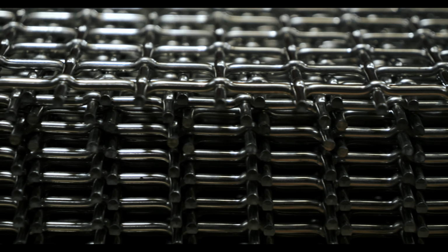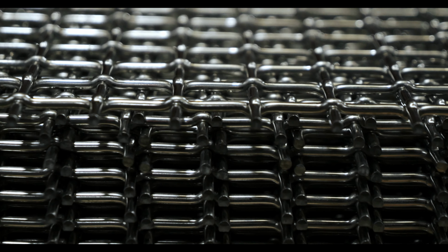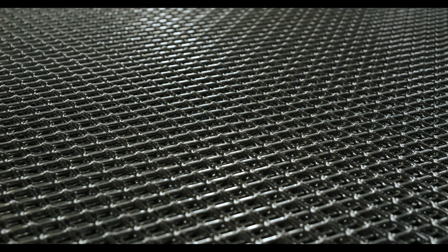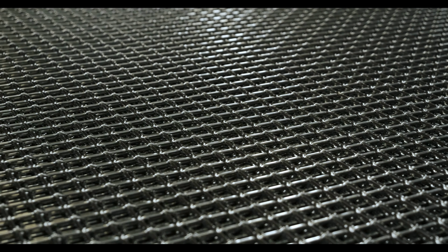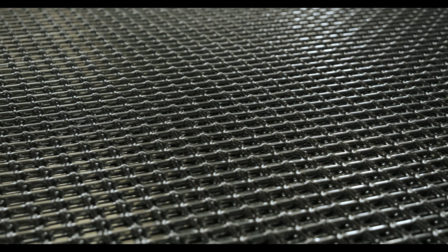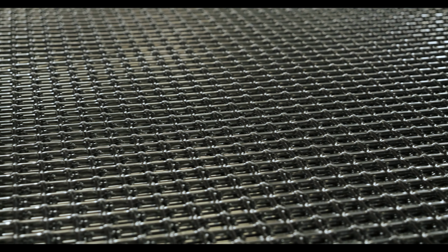Thermal desalination systems require materials that have high thermal conductivity and resistance to scaling and corrosion, making 254 SMO and duplex ideal. In reverse osmosis systems, high pressure and brine exposure is common, so duplex alloys excel due to their strength and resistance to chloride-induced stress corrosion. Plants in tropical or polluted coastal areas may also benefit from super austenitic grades due to their enhanced resistance to biofouling and aggressive seawater chemistry.